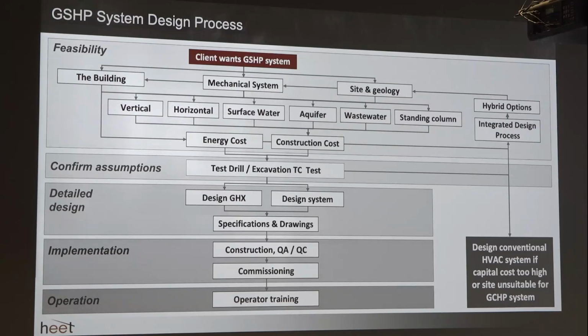So when you have a customer or anyone, frankly, who's interested in a geothermal system, where do you start? If they say, hey, Connor, I've heard of this geothermal technology, I've heard it's pretty cool. What do I do? Well, you'd probably want to start with the building, right? Again, determine your total demand to determine your supply. And then you can start looking at your mechanical system, your geothermal mechanical system, and your site and geology. The site and geology is going to dictate what type of ground heat exchanger you go with. There's many different ways to exchange heat with your external environment. Again, all you're doing is obtaining moderate temperatures so that your heat pump doesn't need to work as hard.